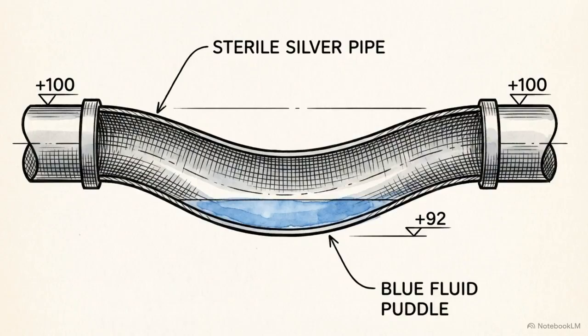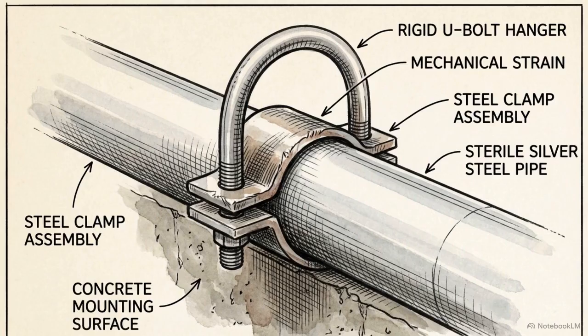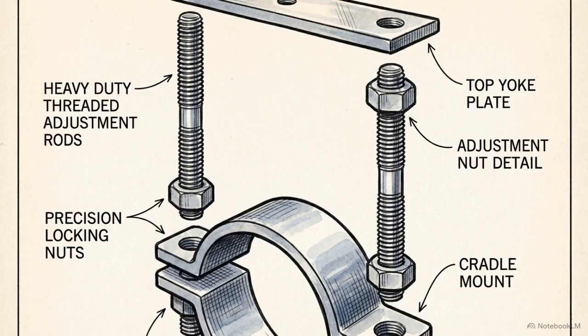This downward pressure can cause the pipe to sag between supports, creating a belly or a flat spot that traps water. Traditional static hangers cannot be adjusted to correct for this gradual deformation, making them unsuitable for long-term compliance. The solution is rigid, adjustable hangers.